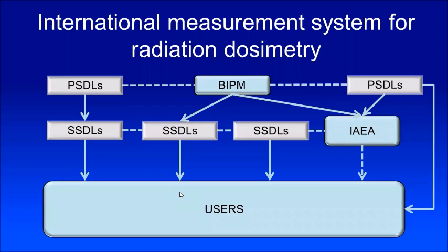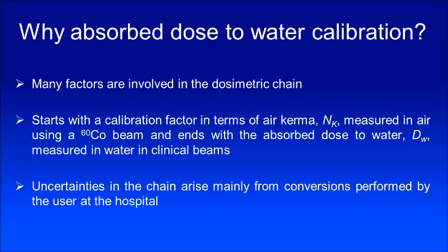This flowchart explains the traceability to the primary standard at the international level. For example, you are the user — you would have calibrated either in an SSDL or at the IAEA. The SSDL would have calibrated with a PSDL, the BIPM, or another primary standard. If your country has a primary standard laboratory, you could also directly calibrate there. The IAEA, primary standard, and secondary standard all have a network and verify dosimeters with each other — so you have traceability.